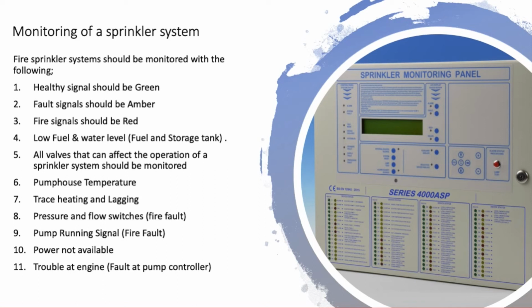Okay, power not available would be a fault signal. And trouble at engine, basically a fault with the pump controller, again would be a fault signal. And that would be for most of the signals. There is a little bit more than that. You would need to check with your sprinkler consultant and your sprinkler installer, and they'll tell you exactly what you should be doing. Okay, so you've installed your system. Everything's, you're happy with it, it's going to work in the event of fire.